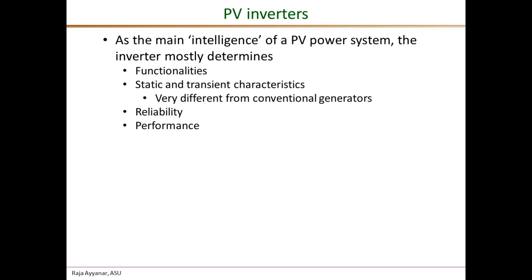The inverters employ fairly high switching frequencies and have large control bandwidths, so they can respond very quickly during system contingencies and be able to provide active and reactive power support, which is a positive thing.